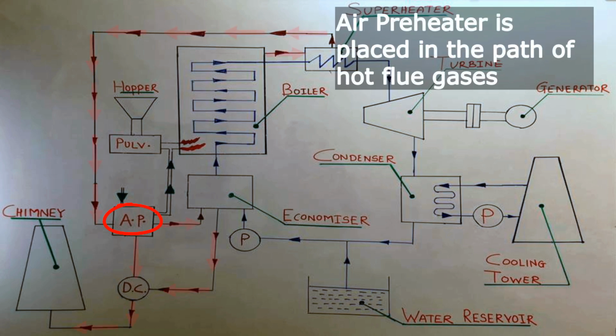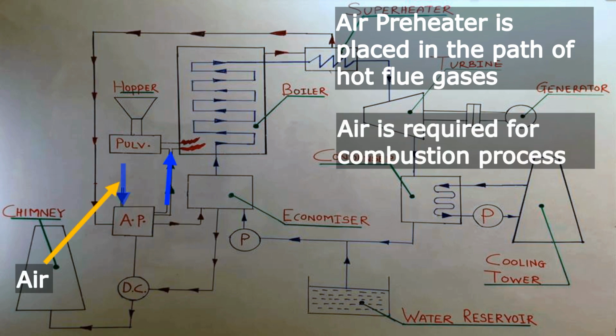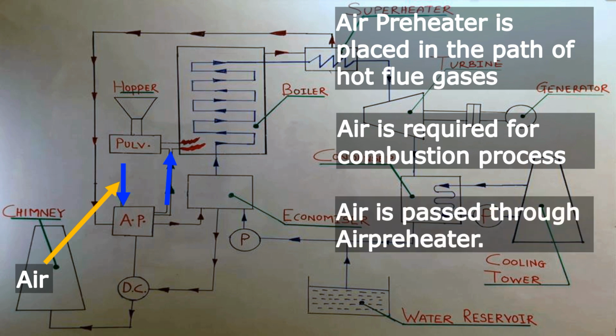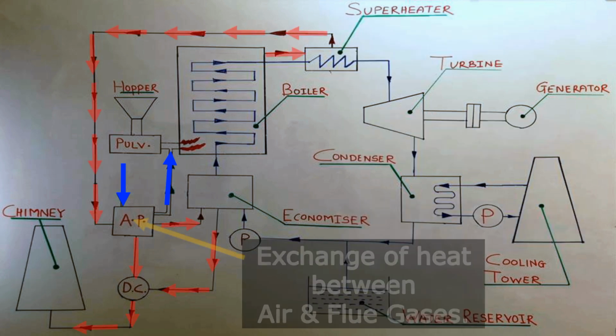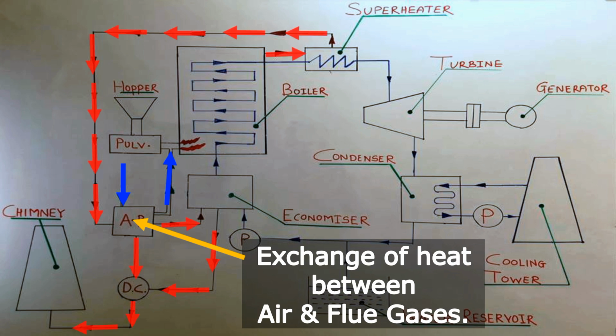We know that for the combustion process we need air from the surrounding. Instead of directly supplying air, we pass this surrounding air through the air preheater. The main function of the air preheater is to exchange the heat of the flue gases with the air in order to preheat the air before supplying it to the furnace for the combustion purpose.